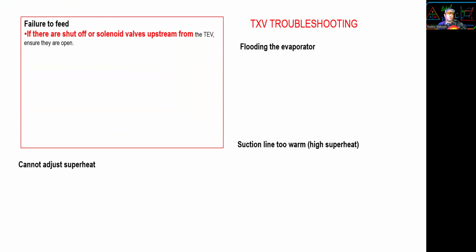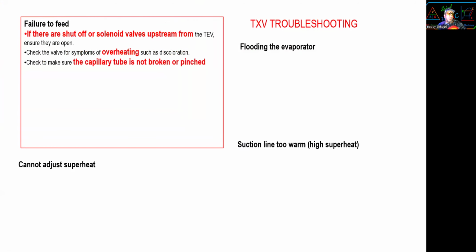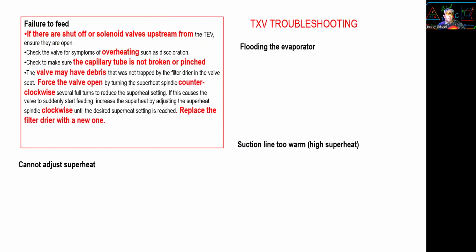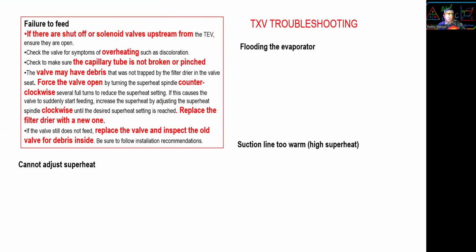If we have a shut off solenoid valve, make sure it's on. Make sure it's not overheating. Make sure the cap tube is not broken or pinched, or the transmission line. The valve may have debris in it. Force the valve open. It says force clockwise, counterclockwise, blah, blah, blah. Then it says replace the valve with a new one. Like I said, it's very rare to adjust it. Replace the valve, inspect the old one for debris inside.